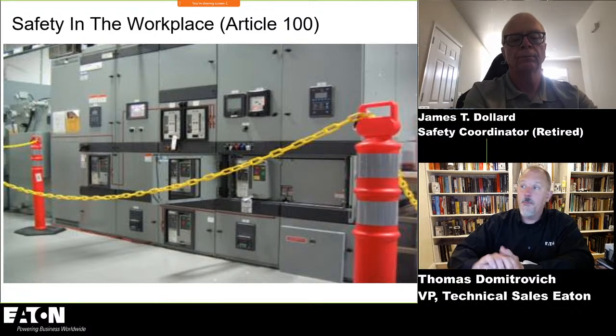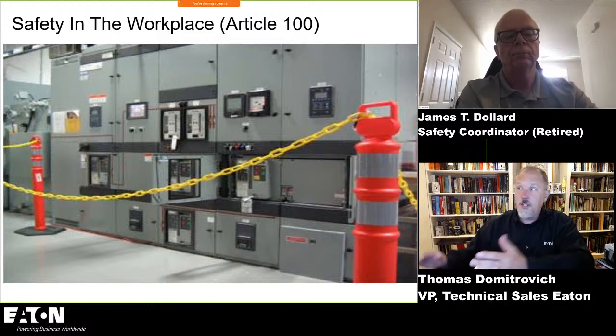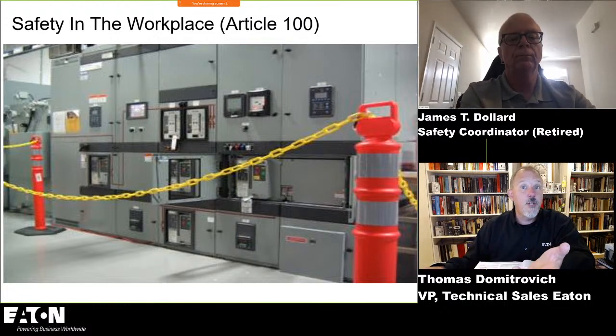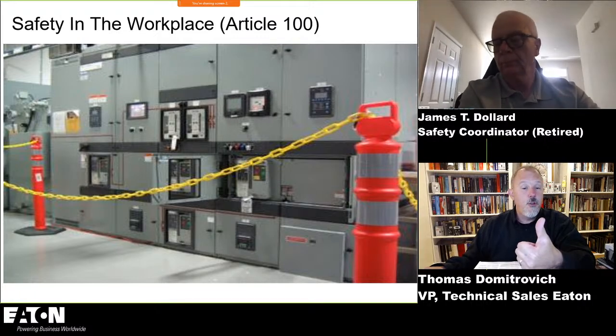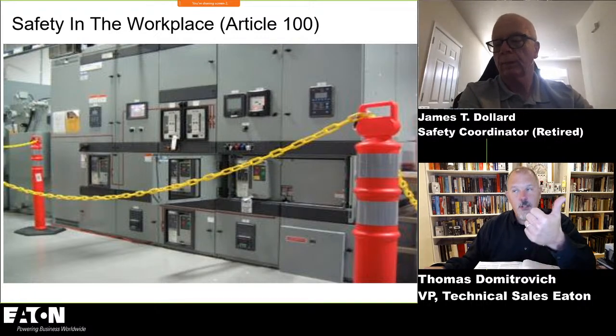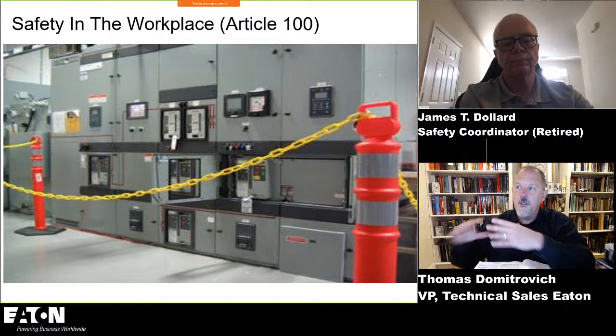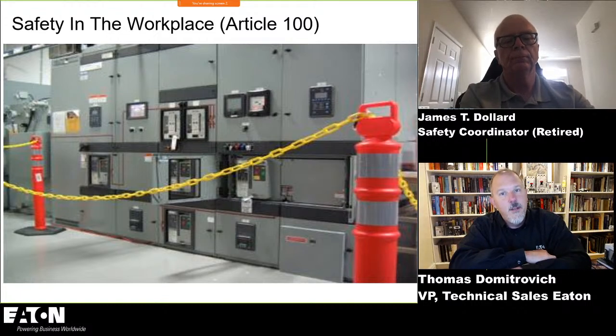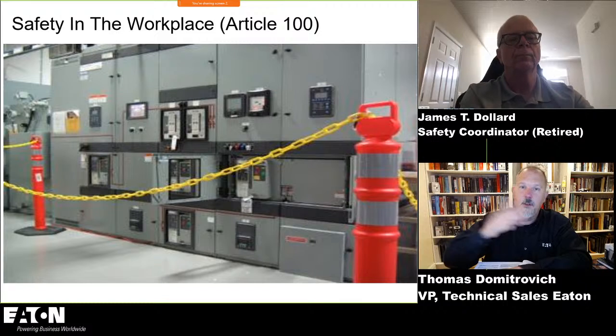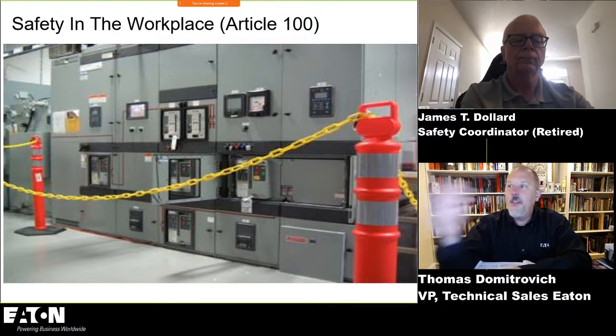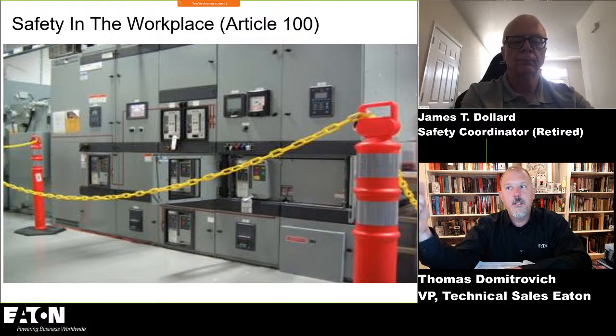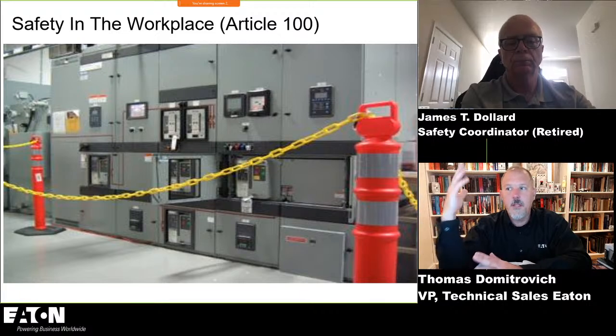And 70E talks about providing barriers and carving out your workspace. So you establish your, what do they call that? You have your limited approach boundaries and your arc flash boundaries, etc. Now, let me ask you, Jim, on job sites that you've been to, do they actually physically delineate where the arc flash boundary is and where the restricted approach boundary is, or is that just something that they know?